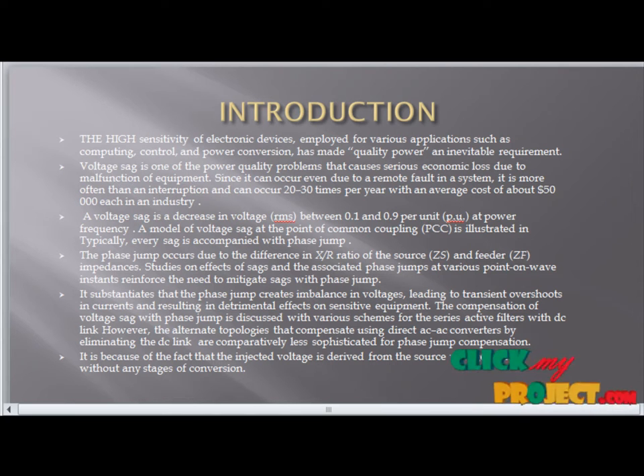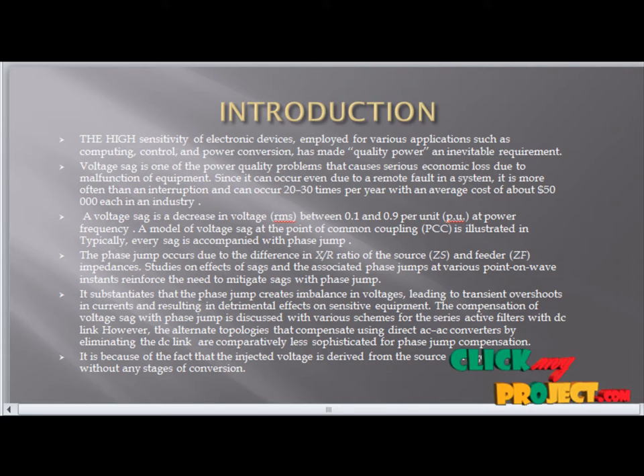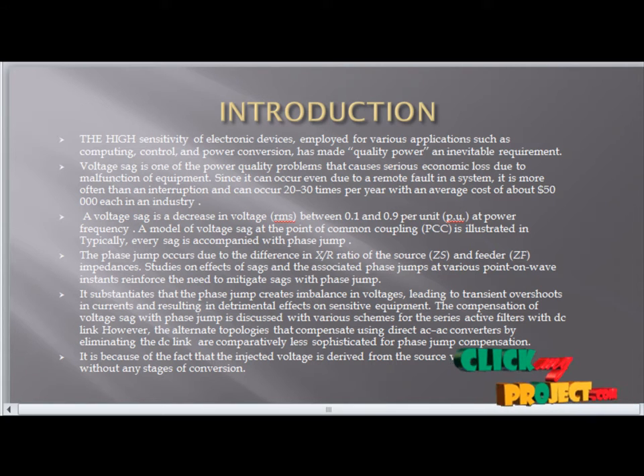The voltage decreases in RMS between 0.1 to 0.9 per unit at the power frequency. The voltage sag model at the point of common coupling illustrates a typical sag with phase jump. The phase jump occurs due to the ratio of source and feeder impedance. The effect of sag associated with the phase jump at various points on the waveform creates imbalance in voltage, leading to transient overshoot.